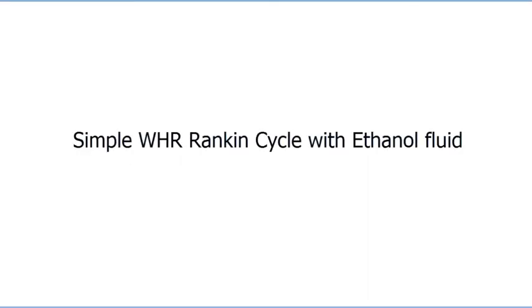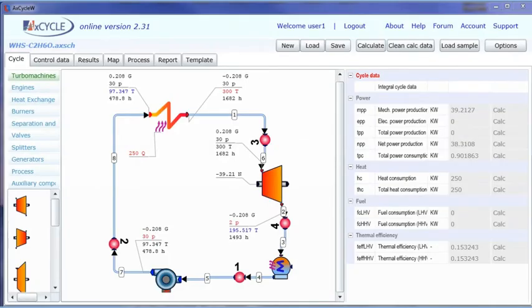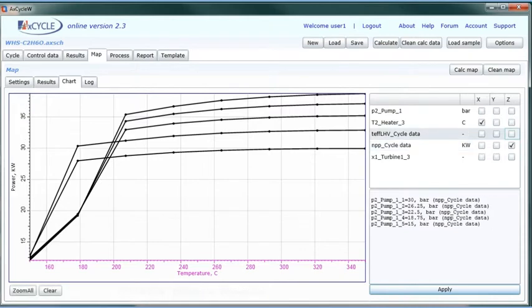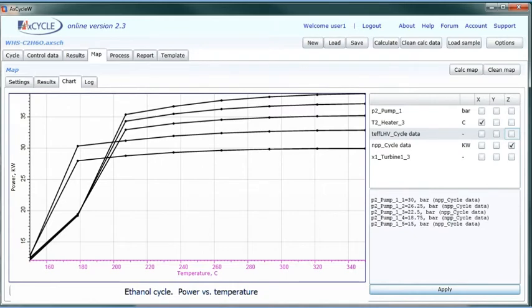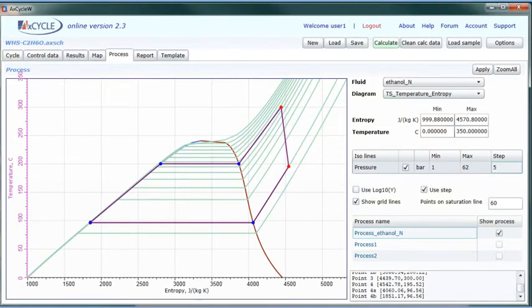The next case shows a simple heat recovery cycle with ethanol as the working fluid. Ethanol features more than twice the allowable temperature compared to R245. Calculation data are presented for an operation point of 30 bar, 300 Celsius. The ethanol cycle power versus temperature plot and efficiency versus temperature plot are shown, along with contours of power versus temperature and pressure that define the operational range. Process shown for 30 bar, 300 Celsius.